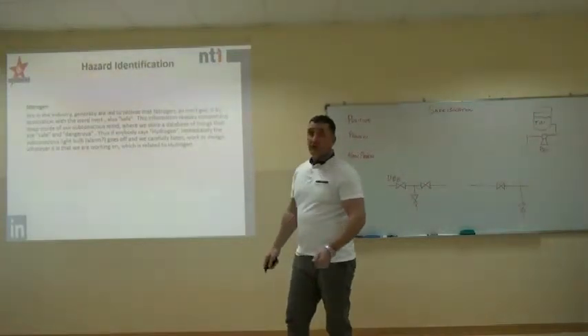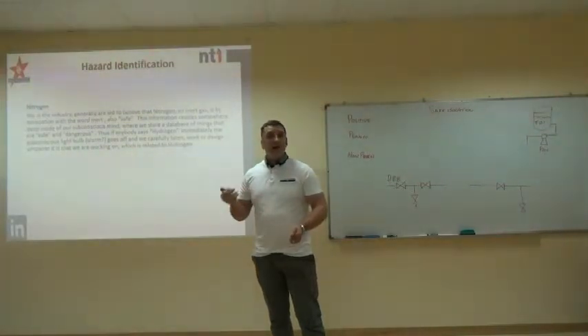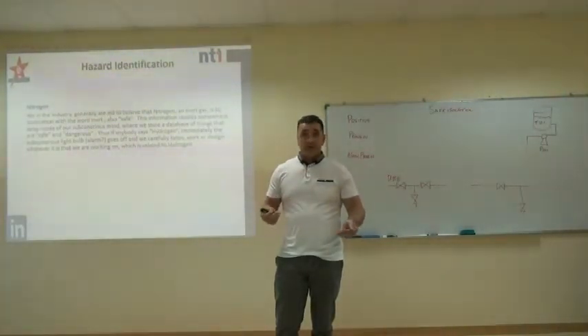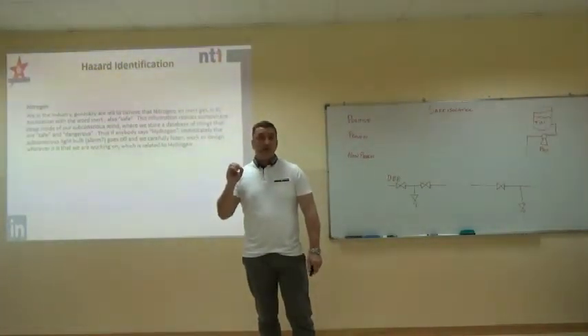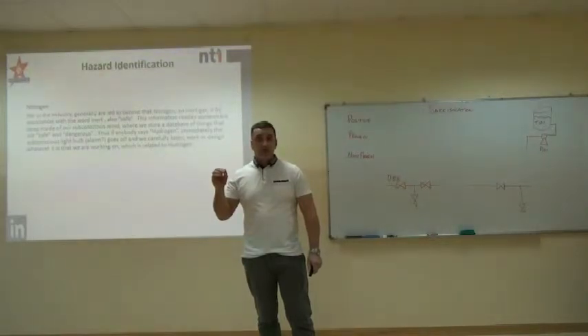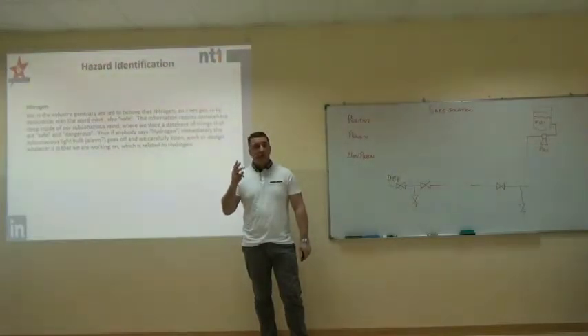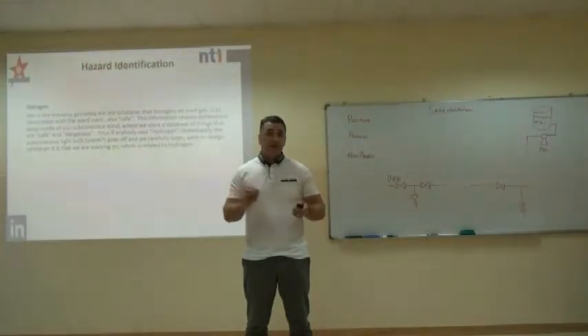Nitrogen: we use it a lot in process for purging and blanketing. Why is nitrogen dangerous? It's an asphyxiant — it displaces the air. A lot of people think it's safe because it's inert and doesn't aid combustion. The air we breathe is 70-something percent nitrogen, but if we breathe pure nitrogen we will be dead very quickly — two or three breaths and you're dead. If you've got a process vessel with a permanent nitrogen connection, that must be isolated too. Lots of people forget to isolate the nitrogen supply.